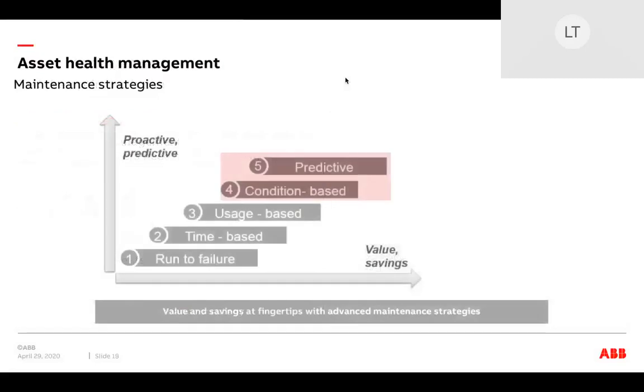What are the maintenance strategies available to you, and what is the cost? You could run to failure and risk total production loss. Not a great strategy. You could move up the ladder and go to time-based, which does not take into account if a breaker has switched once or 300 times in the last year, whether it has been switched or whether it has tripped in anger. Next, you could look at usage-based maintenance. Do I know what my usage is? What the usage reflects? The best option to maximize production continuity and reduce service cost is condition-based, using analytical data that allows you to get up-to-date, holy grail predictive maintenance.